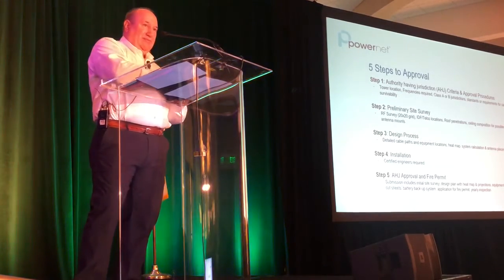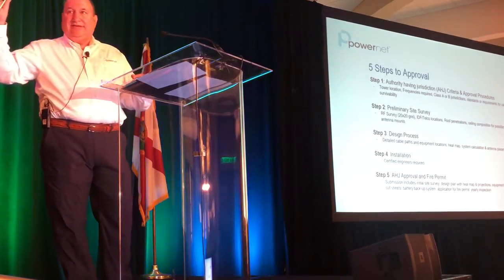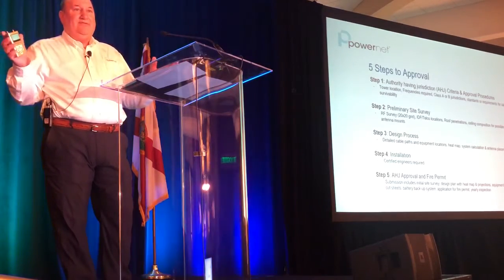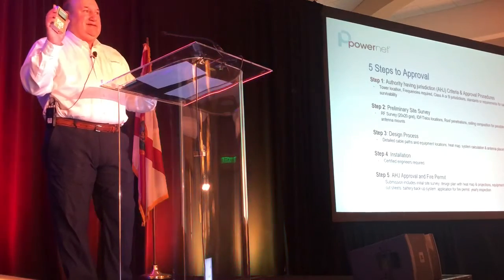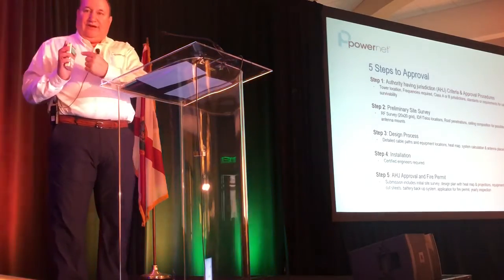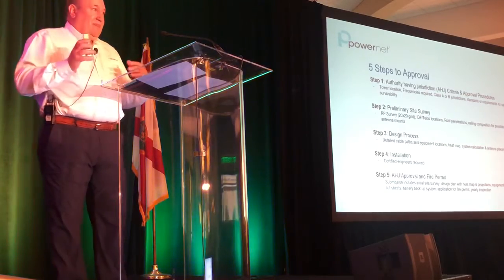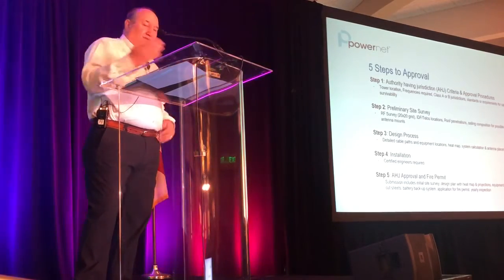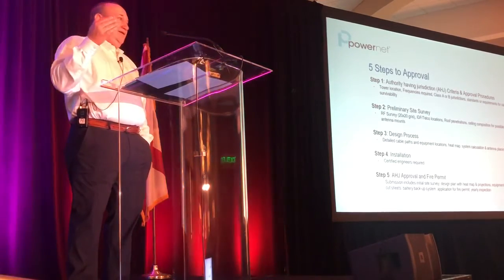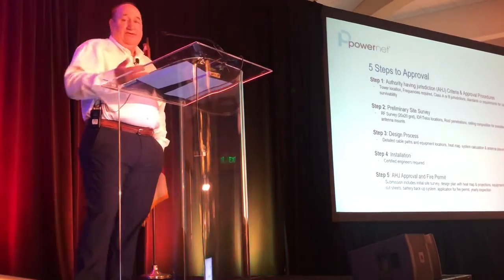They're going to talk to them about where the towers are located, and then they'll come into your facility with a device similar to this, which is a small spectrum analyzer, and there are many of them. We have big ones and little ones. This one is designated pretty much just for public safety. We go in and key in the exact frequency for that local jurisdiction, so we know what our downlink and uplink is. And then we do a site survey of the building, which means outside completely and inside every room in the building, especially critical areas. And then we come back with the results.